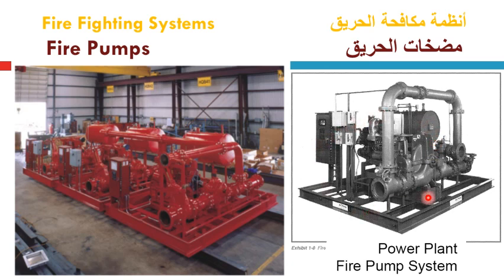This is another one, consisting of one diesel engine driven pump, and the fuel tank is located here, and all the suction line components and discharge line components are affixed on one skid, and the fire pump controller is located here. This skid can be used for outdoor installation, especially for power plant fire pumping systems.